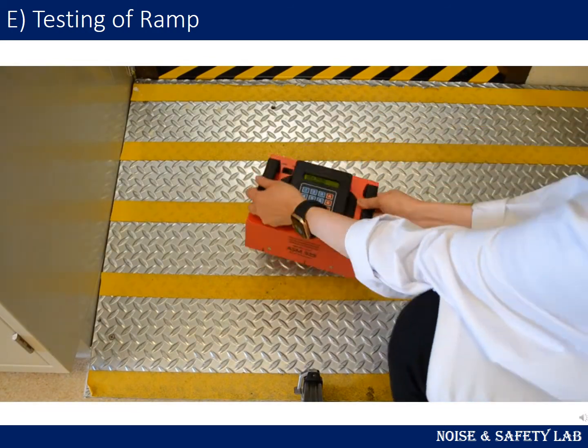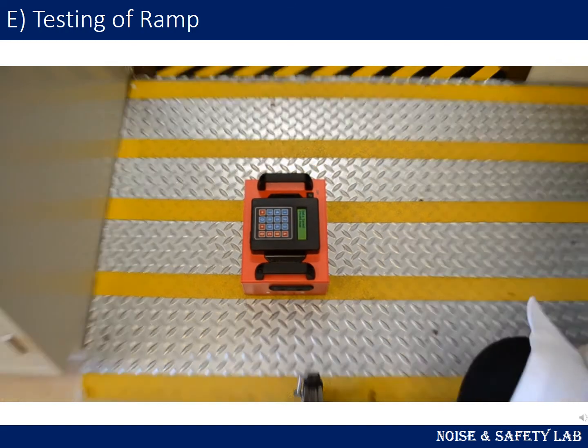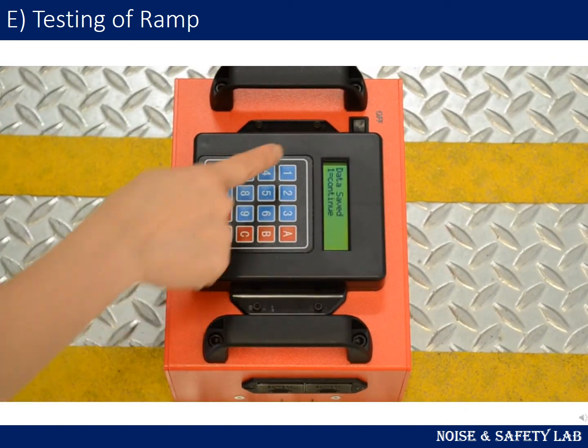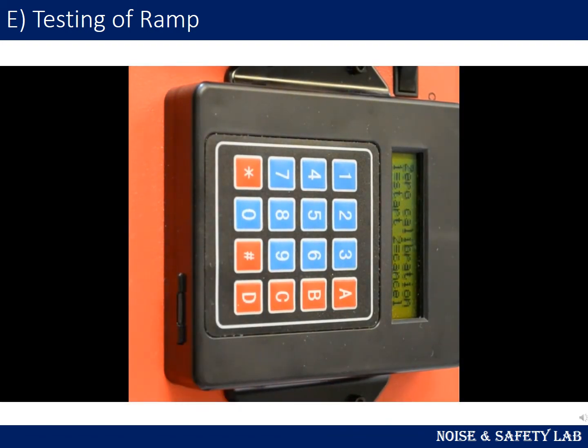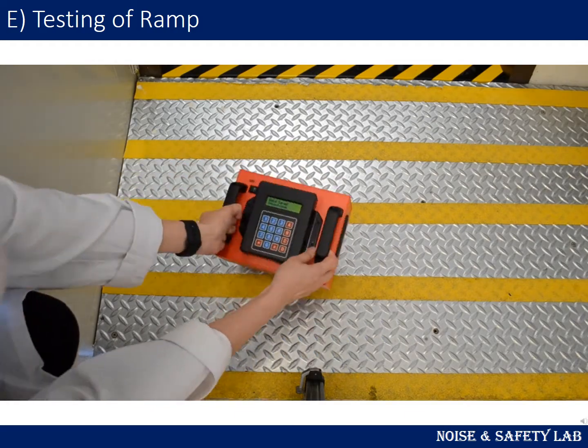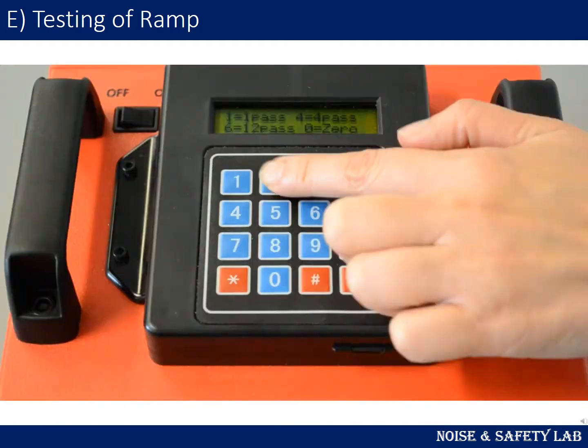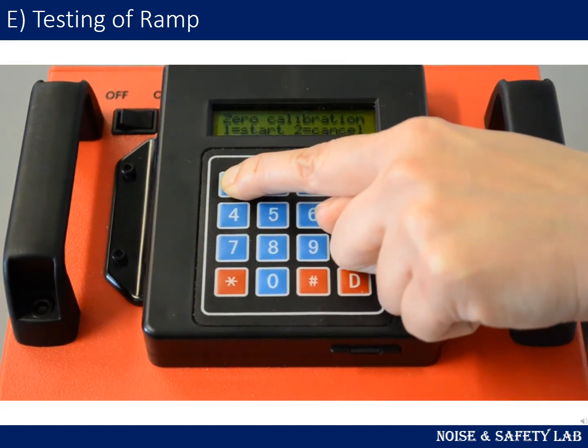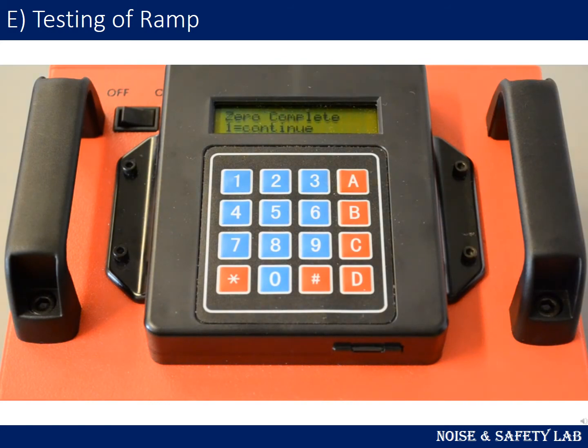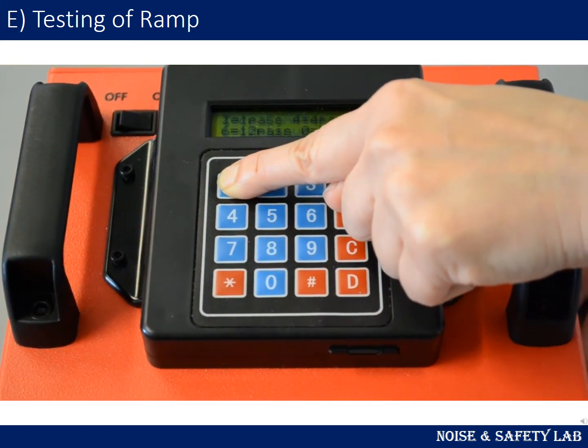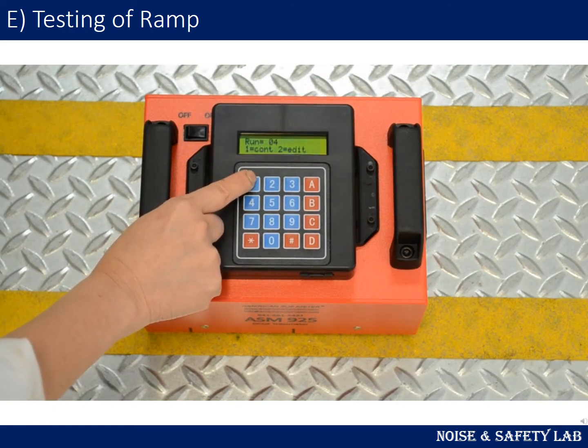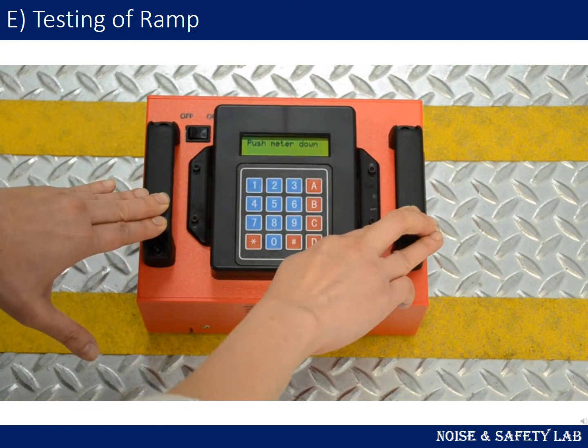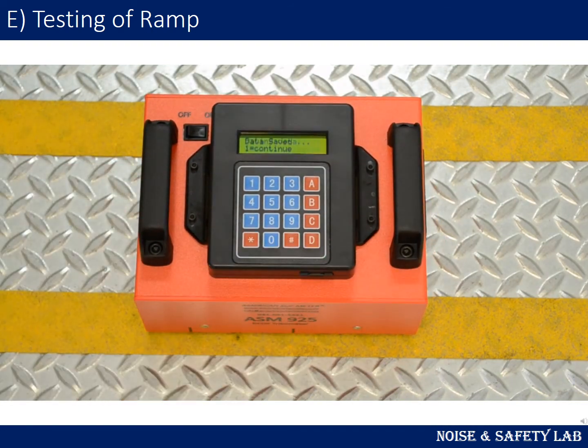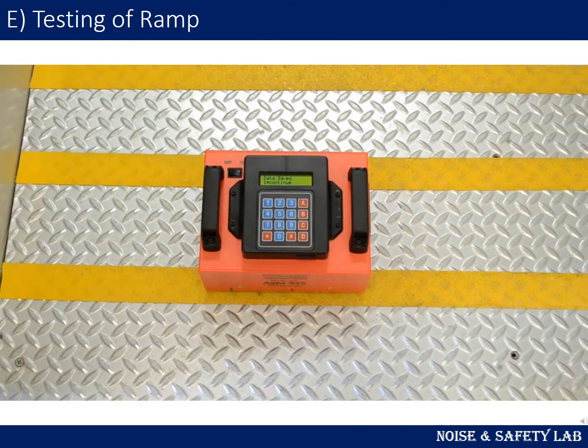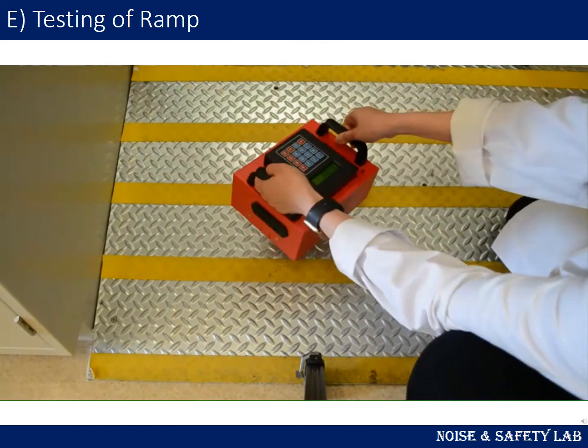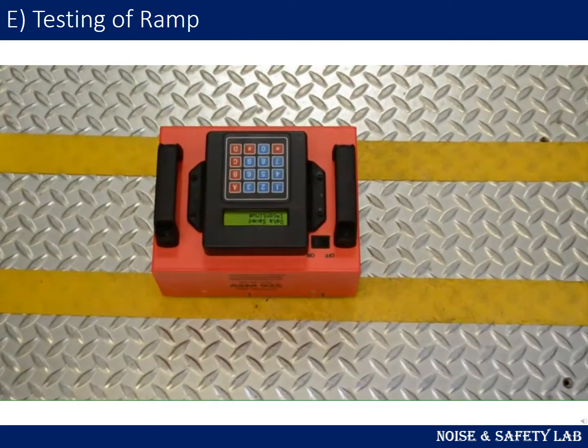When the up-slope measurement is done, turn the meter around by 180 degrees for the down-slope test. At this position, repeat the zero calibration and the single pass test. For the perpendicular to slope test, put the meter across the slope and repeat zero calibration as well as single pass test again. Turn the meter around by 180 degrees for the other direction of the perpendicular to slope test.